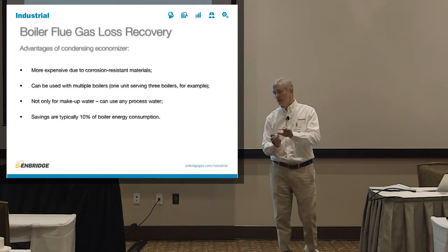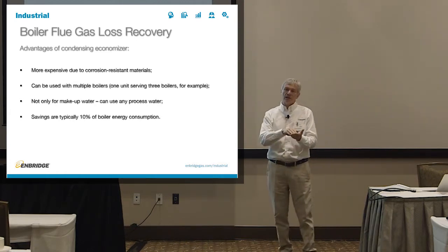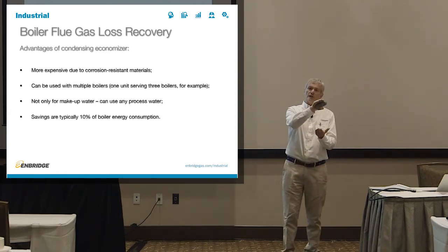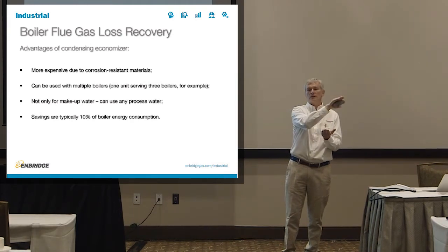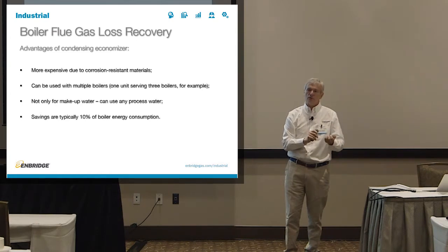Because in our case, the exhaust gas, instead of going from 450 to 350, let's say, and 320 after the feed water economizer, will go at 450 directly into the condensing economizer. And the condensing economizer will lower the temperature down to the same 100 degrees F if it's properly sized.